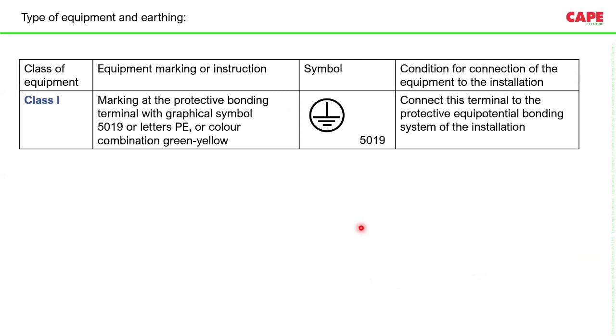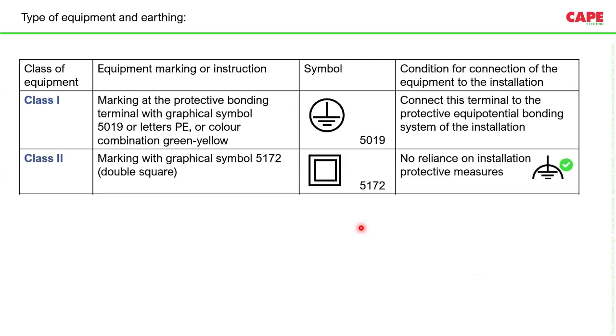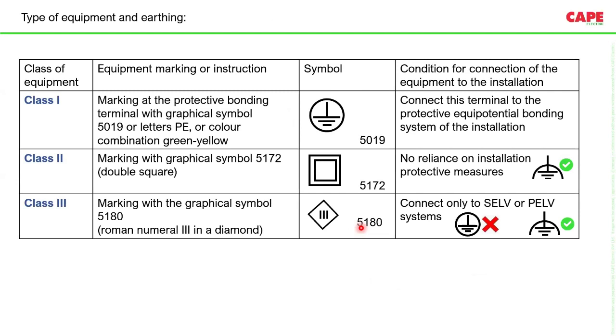When it comes to earthing, one more point you should understand is electrical appliances are of 3 types. In fact, there are 4 types. Class 0 is also there, but nowadays class 0 is banned. So basically, electrical appliances are classified into class 1, class 2, and class 3 appliances. Class 1 devices require protective earthing. Class 2 devices are basically devices with a 2-pin plug. Protective earthing is not necessary, but sometimes functional earthing is required.